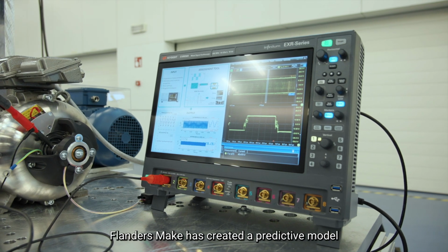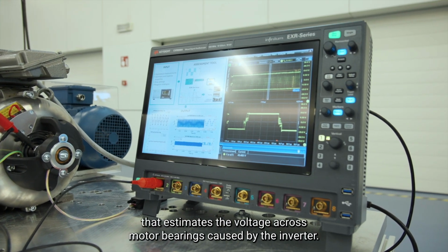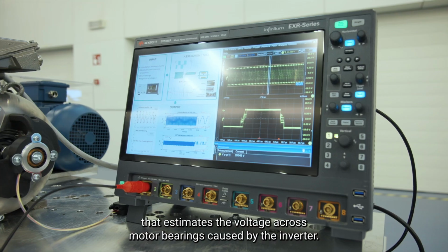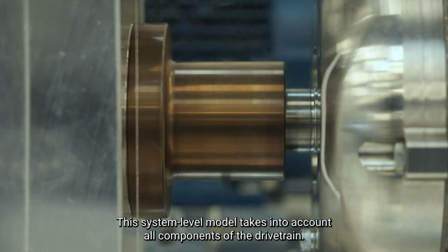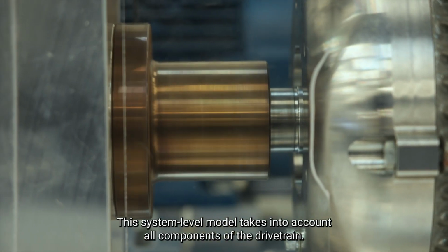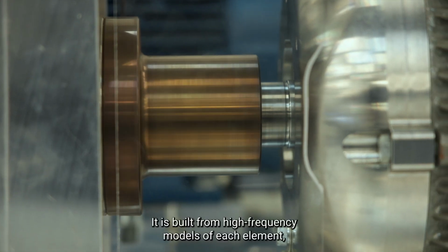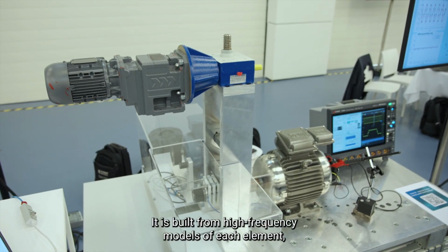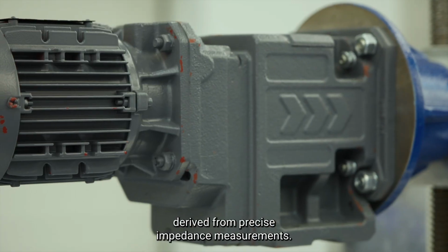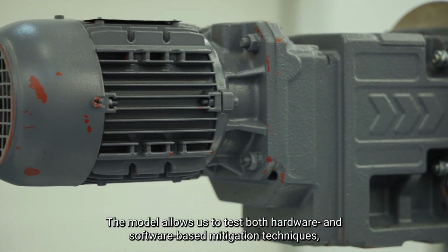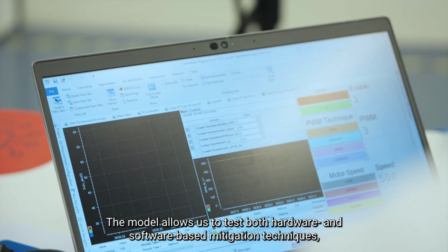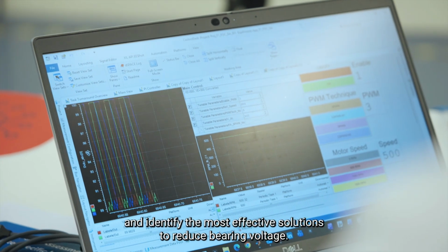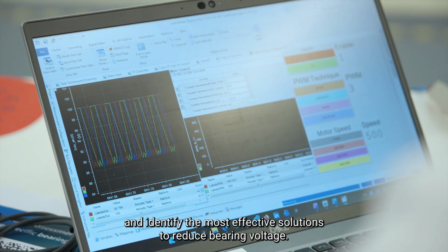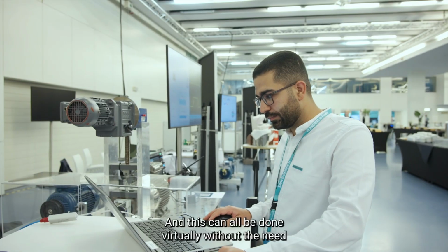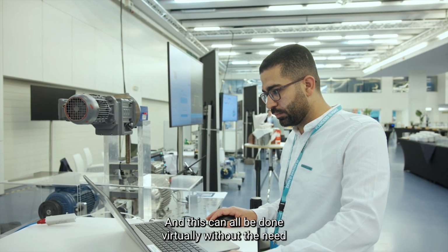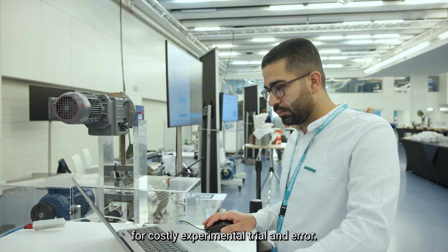Flanders Make has created a predictive model that estimates the voltage across motor bearings caused by the inverter. This system-level model takes into account all components of the drivetrain. It is built from high-frequency models of each element, derived from precise impedance measurements. The model allows us to test both hardware and software-based mitigation techniques and identify the most effective solutions to reduce bearing voltage. And this can all be done virtually, without the need for costly experimental trial and error.